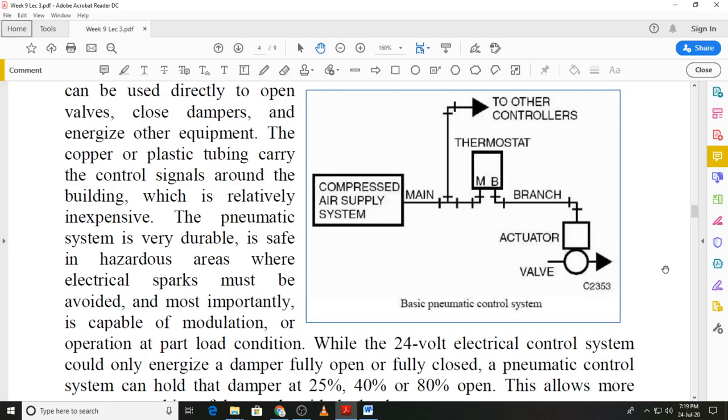So this is again a block diagram of a pneumatically controlled system, in which the compressed air then causes the actuator to function, and then it operates the valve or a damper. The principal advantages of pneumatic air is that, of course, the air is cheap, and it's very durable and safe, especially in hazardous areas where you do not want any possibility of electrical sparks.